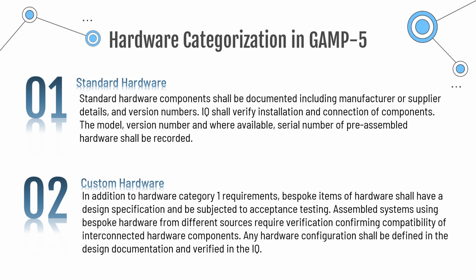Category 2 Custom Hardware. In addition to hardware Category 1 requirements, bespoke items of hardware shall have a design specification and be subjected to acceptance testing. Assembled systems using bespoke hardware from different sources require verification confirming compatibility of interconnected hardware components. Any hardware configuration shall be defined in the design documentation and verified in the IQ.